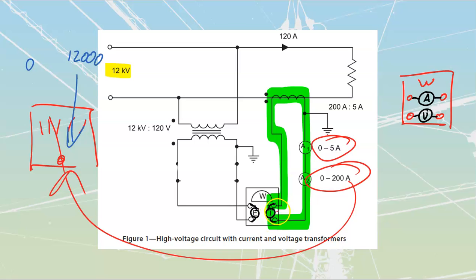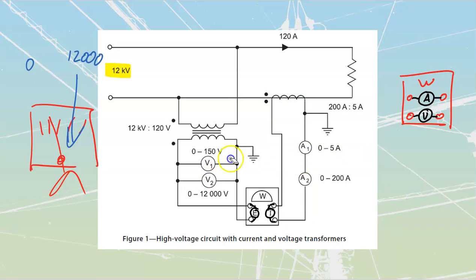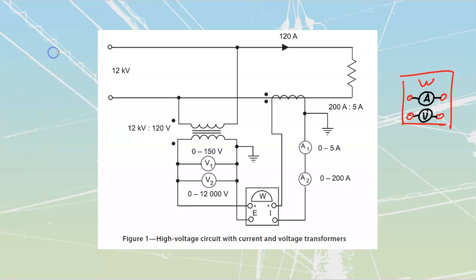The last ammeter section inside of here that completes that circuit is just going to, through the internal electronics inside that watt meter, make that multiplication to become wattage. It looks confusing the first time that you go through, but if you take a look at each individual meter itself, it's really not so bad. What we are going to have inside of here as well is a ratio or a multiplier that we are going to create for this whole circuit. And that multiplier is going to be based upon what these are going to be. Over here I've got a 12 kV to 120, and over here I've got a 200 to 5.